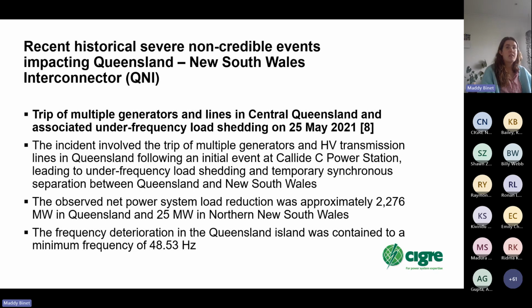The incident involved Callide Power Station, a thermal coal power plant in central Queensland with two 350 megawatt generating units at Callide B and two additional 466 and 420 megawatt generating units at Callide C. The instigating part of the event was that the C4 generating unit's boiler, turbine and field switch had tripped, but its generator circuit breaker had not, leaving the generator motoring asynchronously on the power system, absorbing approximately 50 megawatts and 300 megavar.